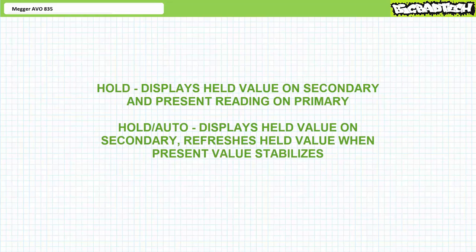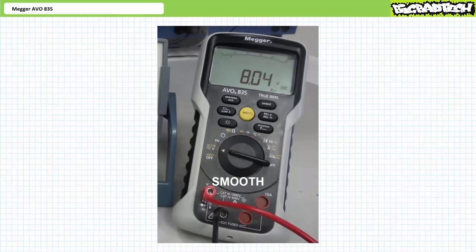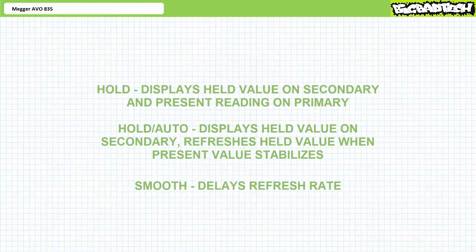The Smooth function simply slows down the display refresh rate. For example, this power supply is presently set at 8 volts. If I turn the dial back and forth a couple times and then ramp it up to 11.5 volts, the voltmeter in Smooth mode just sits back and lets me have my fun. After I settle down, the voltmeter takes another measurement and indicates voltage is presently at 11.5 volts. These related functions are great for rapidly changing systems when a user just needs a simple reading. As with other features, if you're in Hold, Hold Auto, or Smooth mode and want to get out of it, press and hold the same button that got you there to return to normal measurement mode.